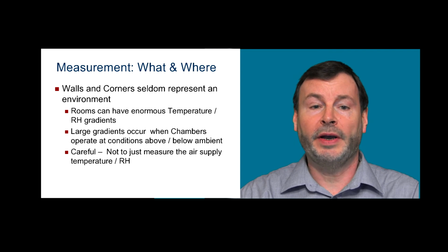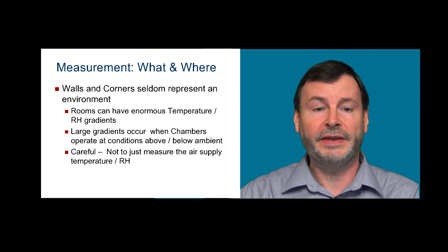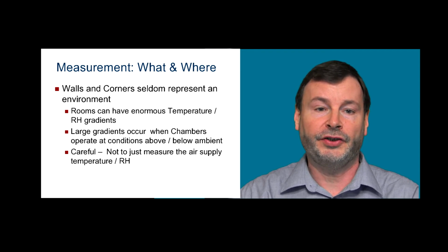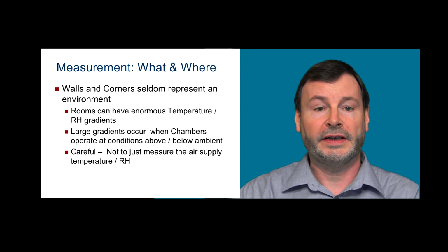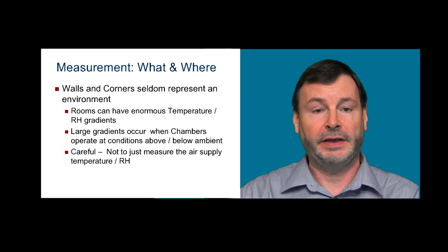And large gradients can occur even within a chamber, particularly if the chamber is running at a temperature different from ambient. If a chamber is well below ambient or well above ambient, we can expect significant gradients, particularly along the walls or in the corners.